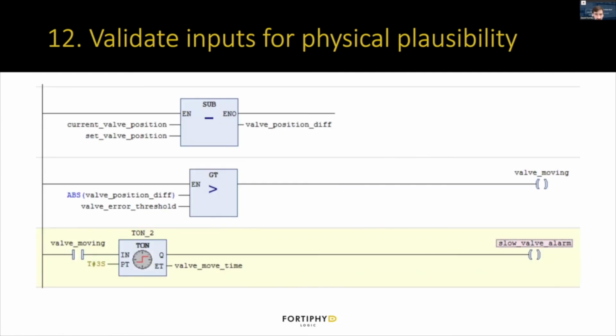And looking at an example in CODESYS, we have some valve positions. We have the current valve position and the set valve position. If the difference between those positions is non-zero, that means the valve is currently moving. And we have a timer here to monitor how long the valve is moving. So in this scenario, the control system is setting the valve to a specified position, and we're monitoring how long it takes to get to that position. If it ever takes 3 seconds or longer, then this timer block will enable this slow valve alarm. It'll just say the valve took at least 3 seconds to actually get to its correct position, so something isn't quite right. The valve is taking too long to get to the set point.